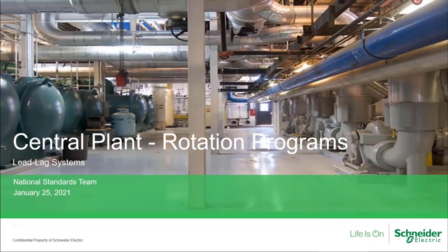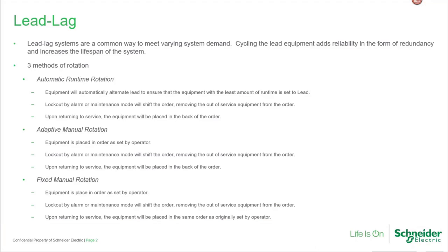Thank you, David. Like David discussed, we did create a program. Our rotation program is basically our lead lag program. So all of our staging and enabling will be handled with other parts of the program. But in our lead lag program, we have three methods of rotation. Okay, our first method is our automatic runtime rotation.